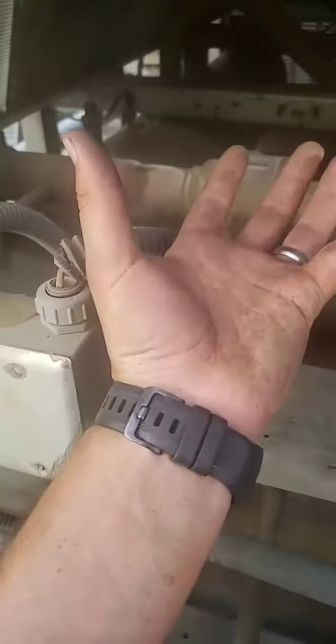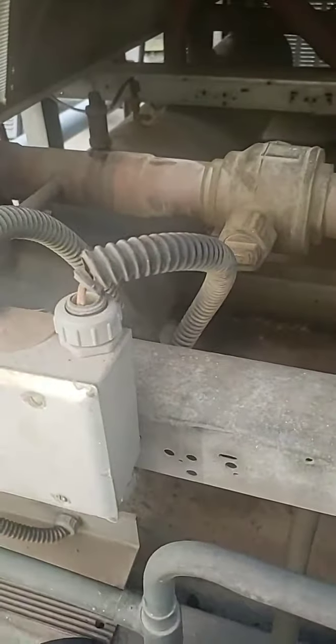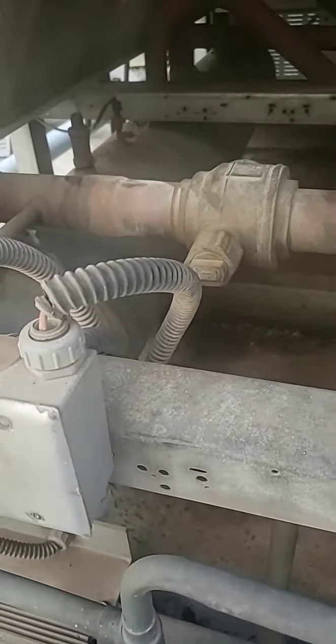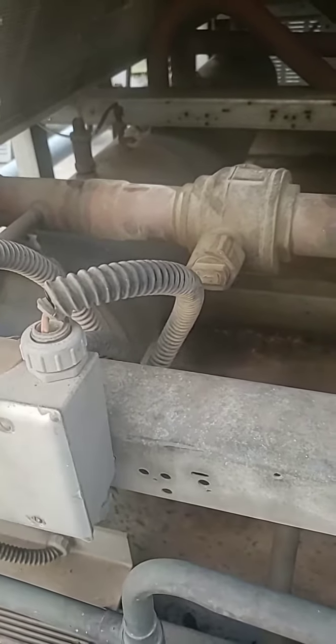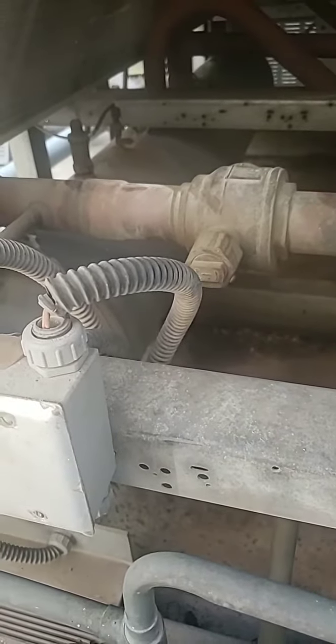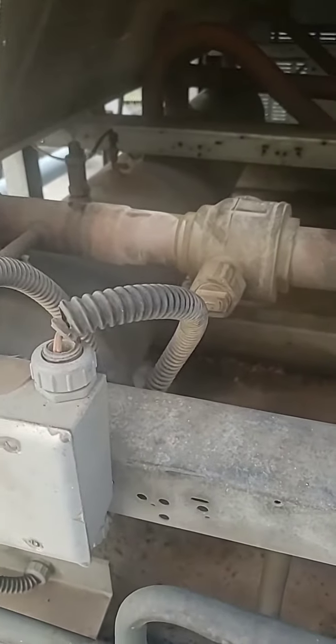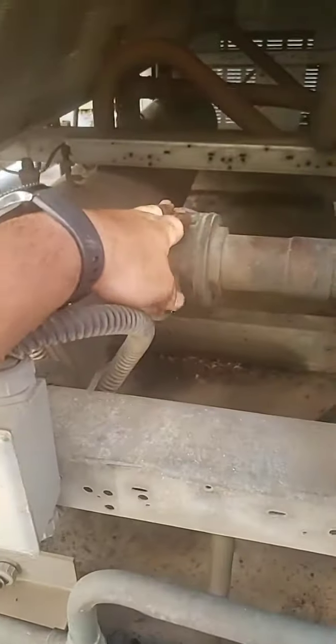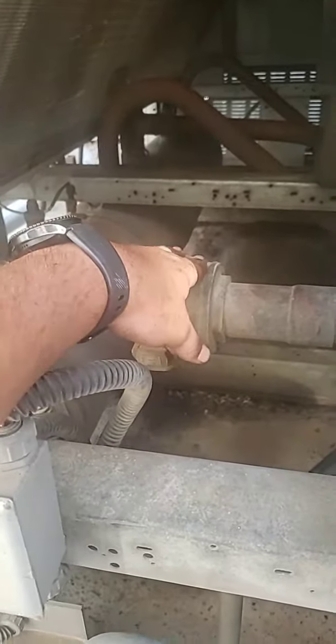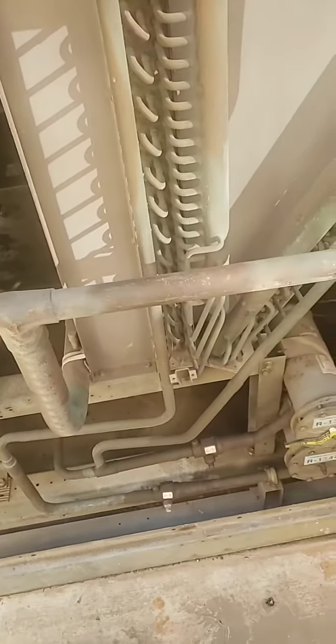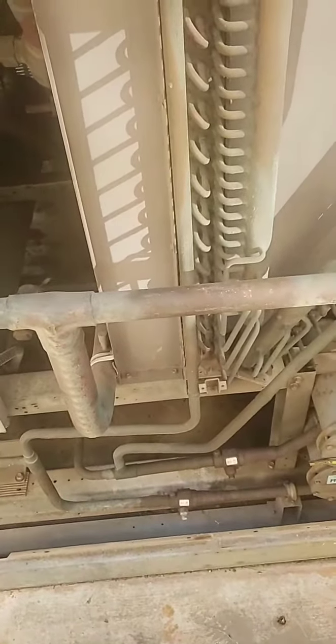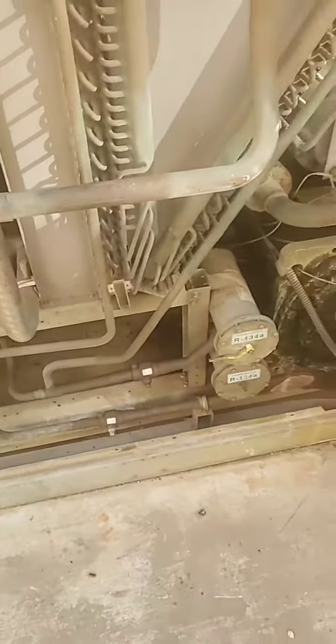It's got a heating blanket on the bottom that just wraps around the bottom of the separator and keeps that oil nice and warm. That does better for the compressor. It also helps prevent any liquid from settling inside, so it does a variety of jobs. You can see this is a discharge ball valve. You've also got another one over here on the liquid. By closing those two, you can isolate the whole condenser assembly. That way, if you ever had to service anything on that side, you'd be able to isolate it from the evaporator.